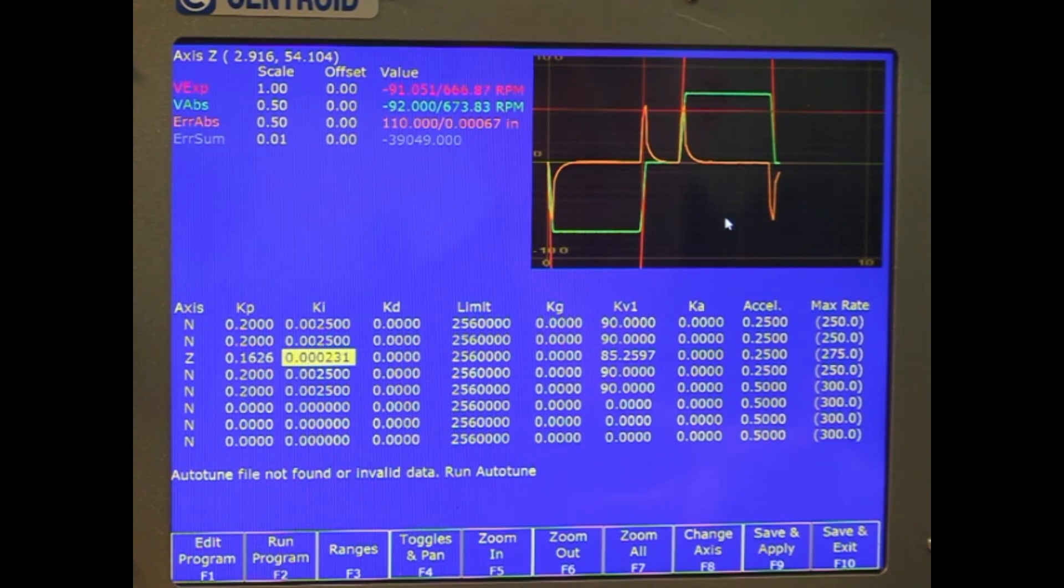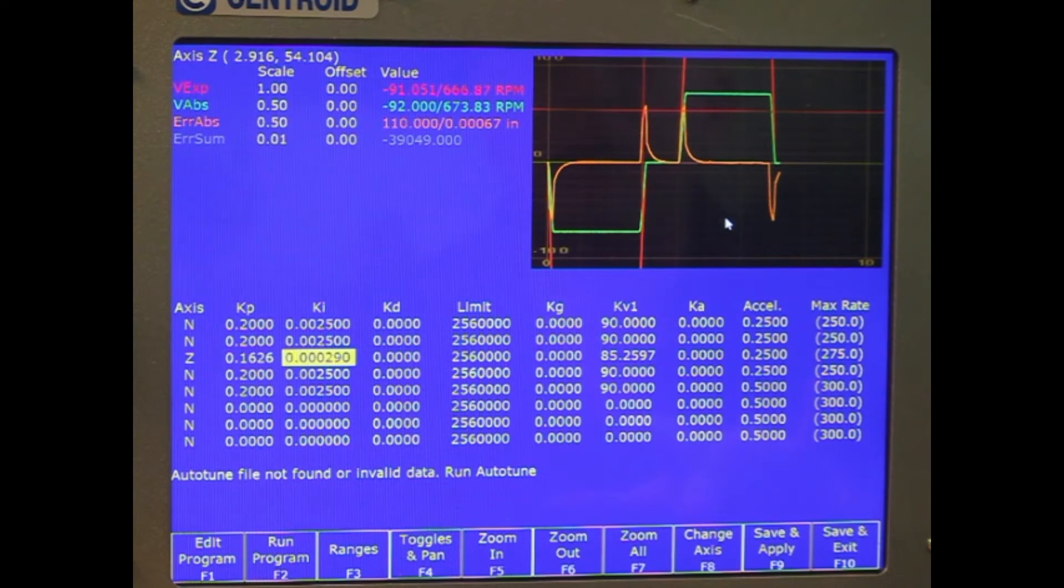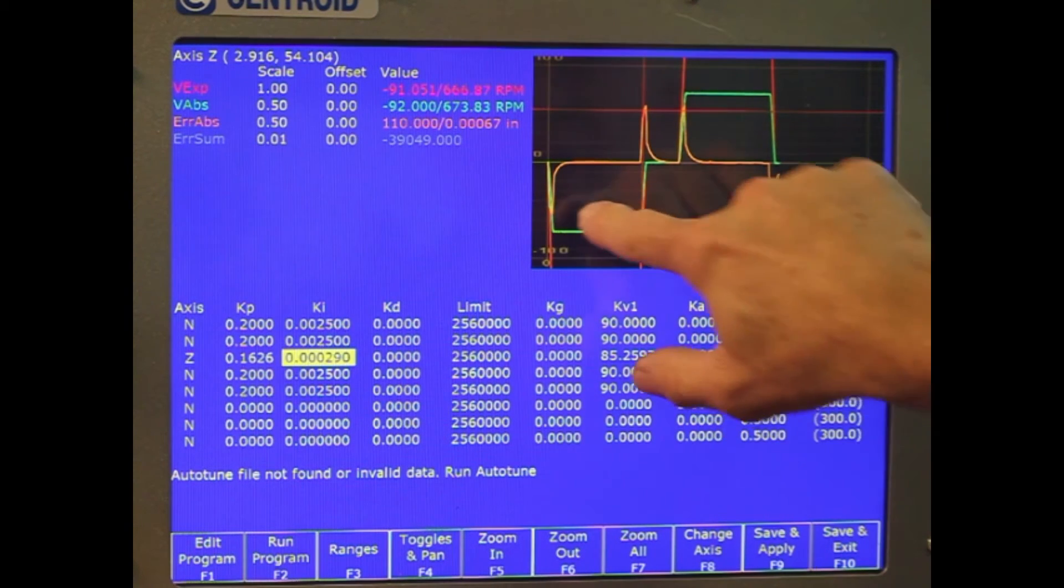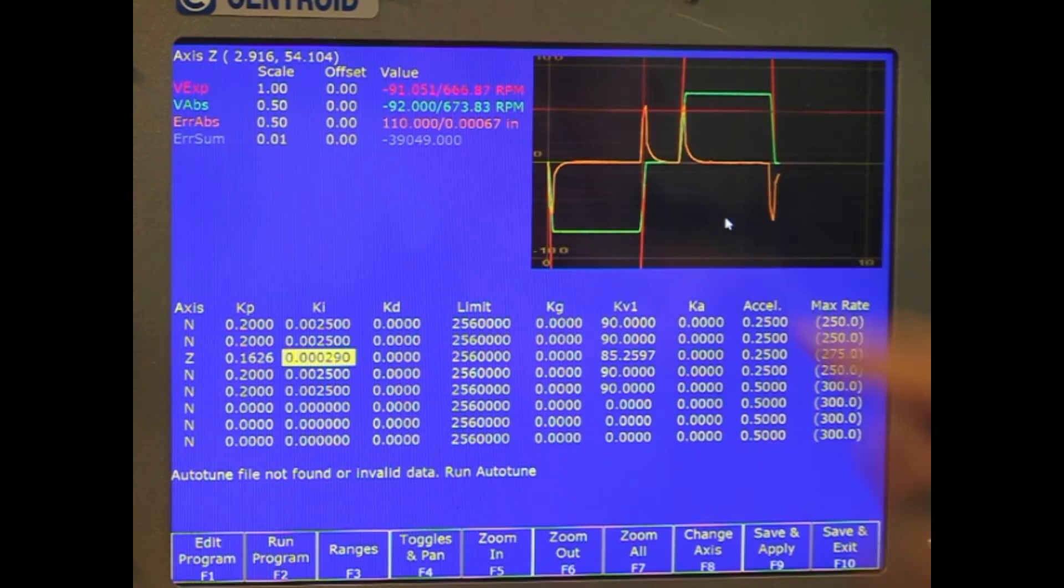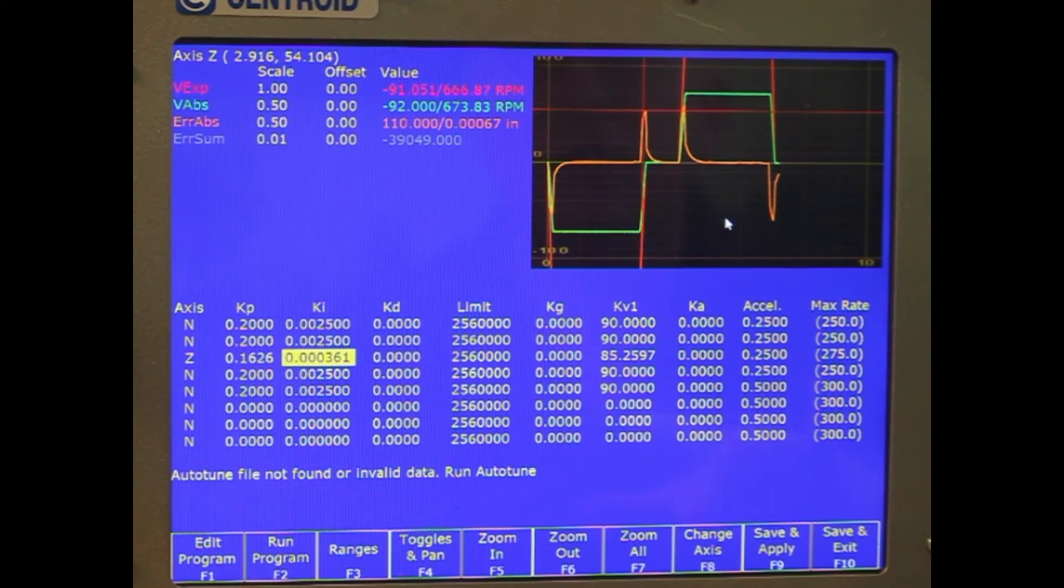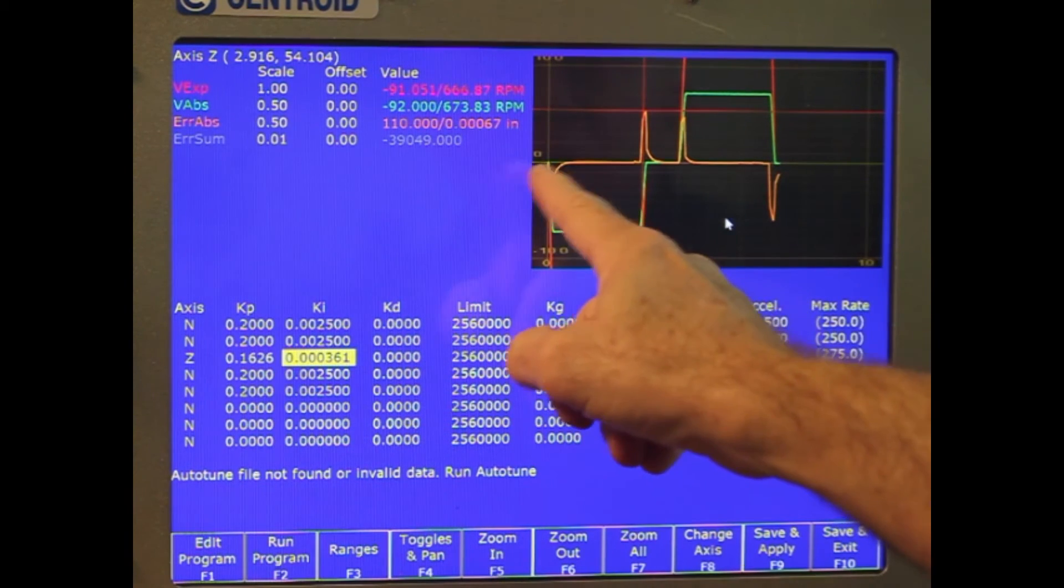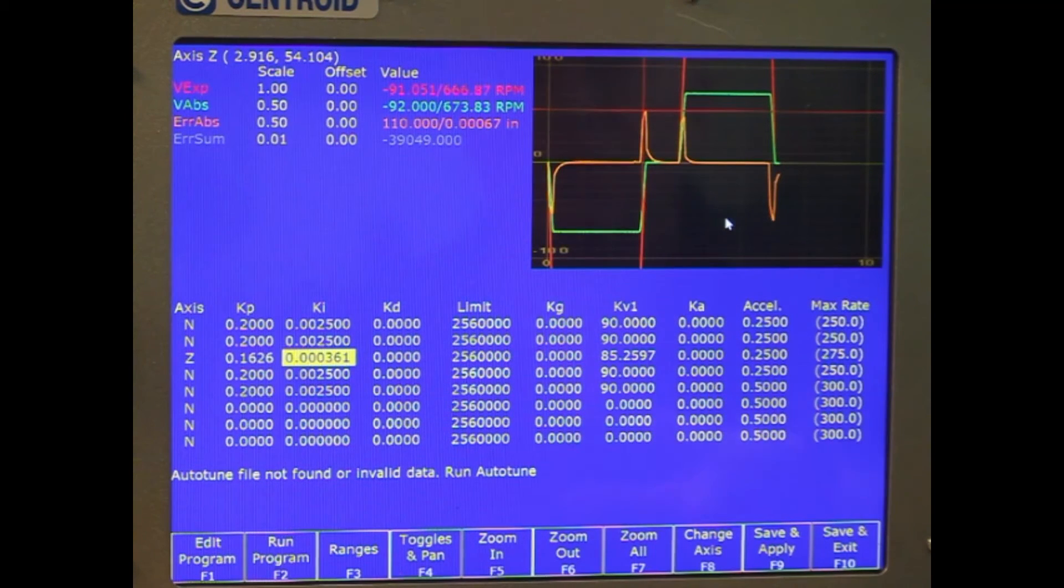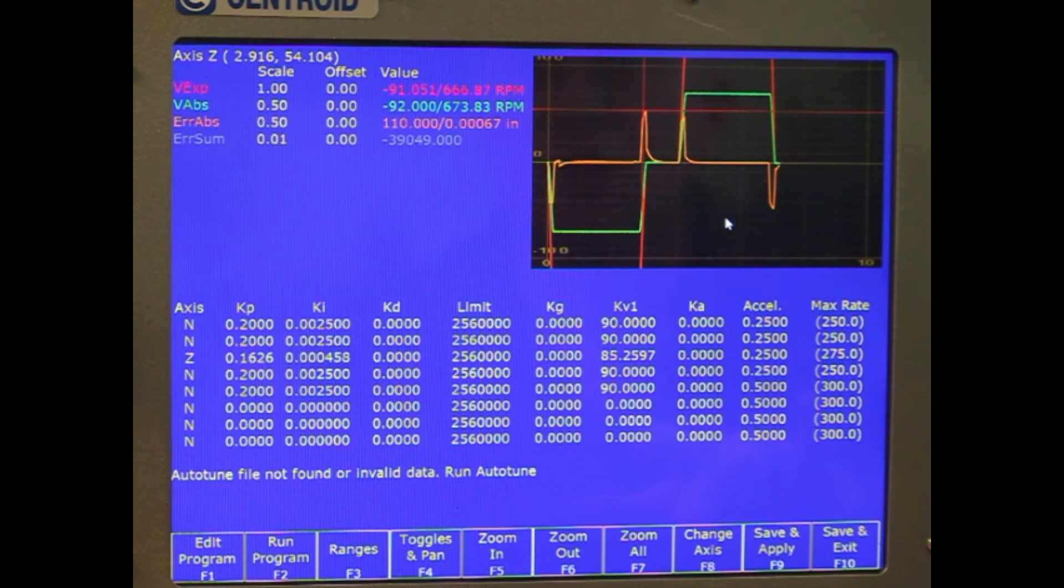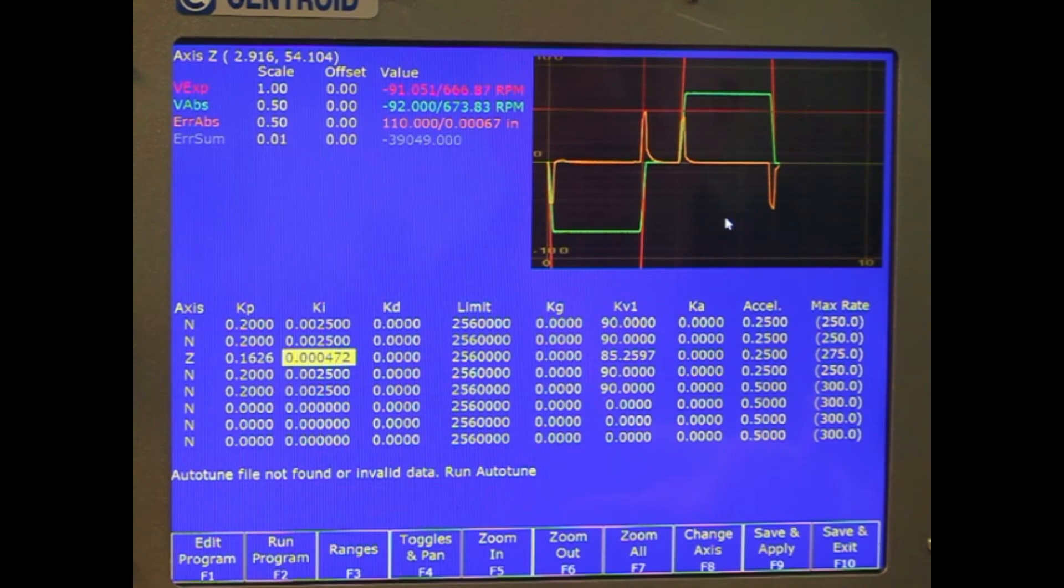So you want, if that's the case, you want to increase your KI to get this bump down to be smaller, so it doesn't take as long. Time base is this way. Each one of these marks is one second. So that it doesn't take as long to actually get itself back into position.